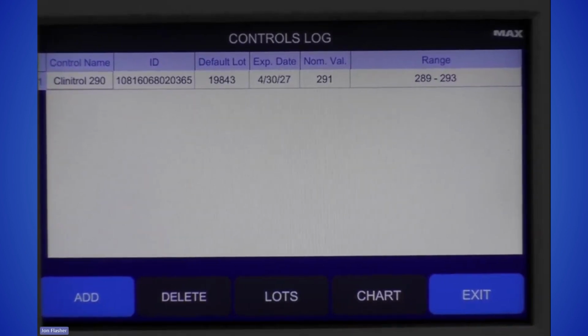Okay, so all that I have logged into this instrument right now is a Clinitrol 290 control. So you can see it gives you the ID, the lot number, expiration date, nominal value, so your C of A value, as well as your range within one standard deviation of the nominal value. So that's all of the information that it shows there.